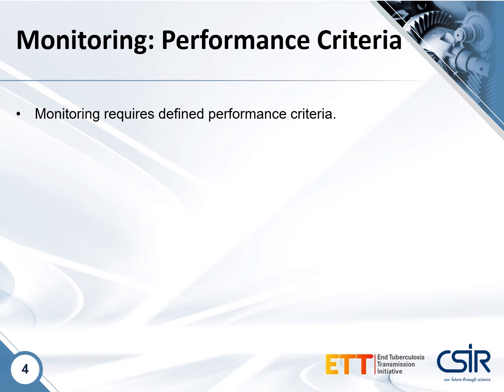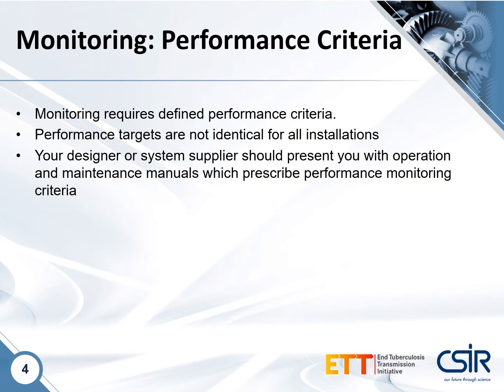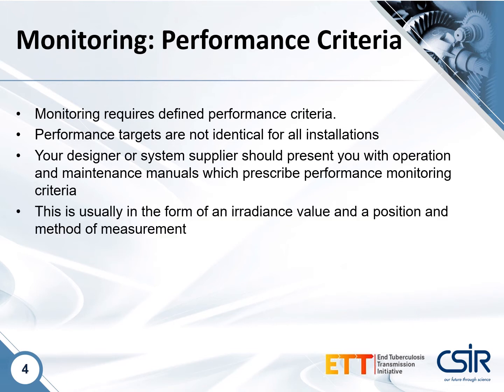In order to monitor your UVGI system, you require predefined performance criteria. This is because your performance criteria for every system you may encounter is not identical, and your designer or system supplier should present you with operation and maintenance manuals which prescribe the performance monitoring criteria. These performance monitoring criteria are usually in the form of a minimum irradiance value with a defined position for the measurement of that irradiance value, as well as a method of measurement, including measurement equipment specifications.